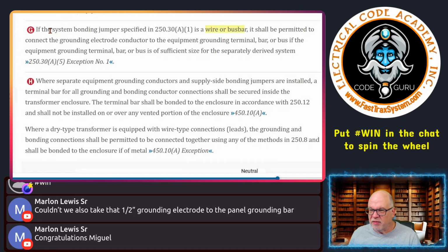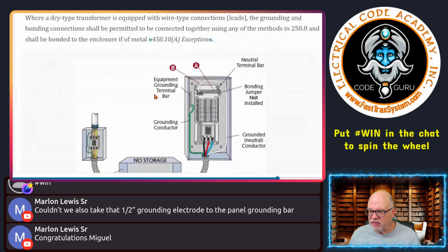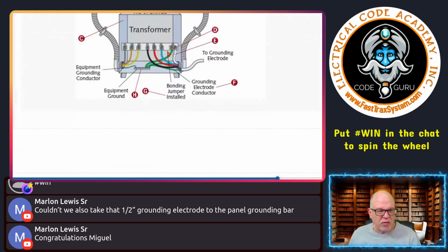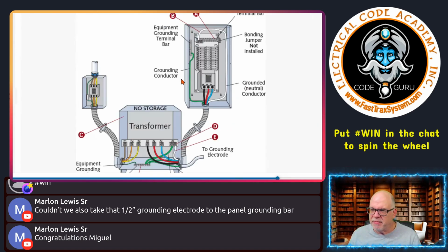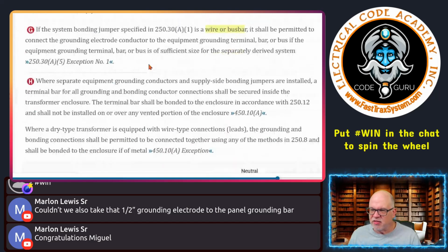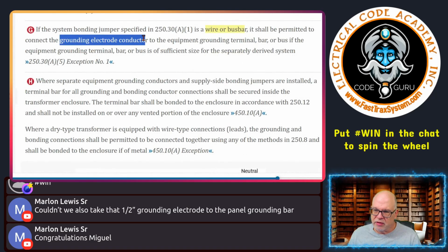where the system bonding jumper is of the wire or bus bar type. So that's what this one is, by the way. This is a wire type. Could be integral bus bar, made in there, does the connection by linkage, could be, but that's of the wire type. What it's basically saying is, I'm permitted to take my grounding electrode conductor.